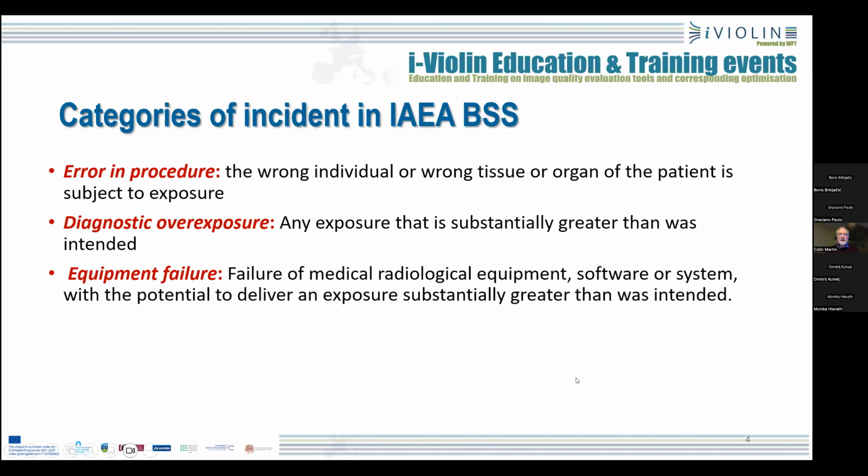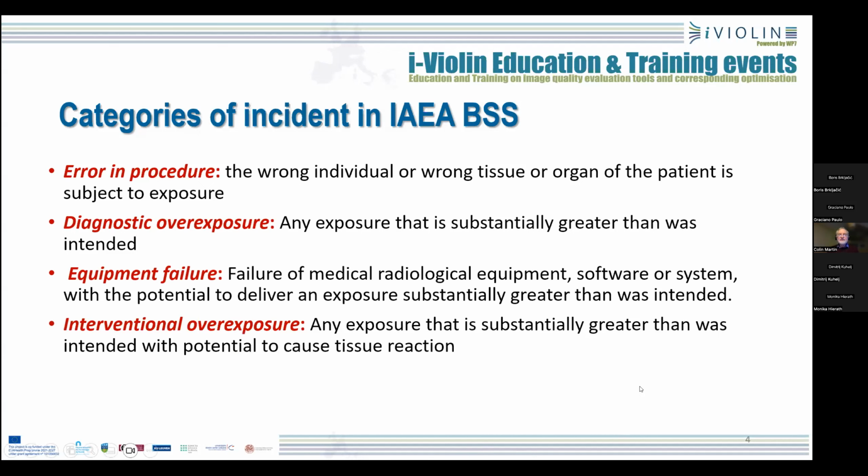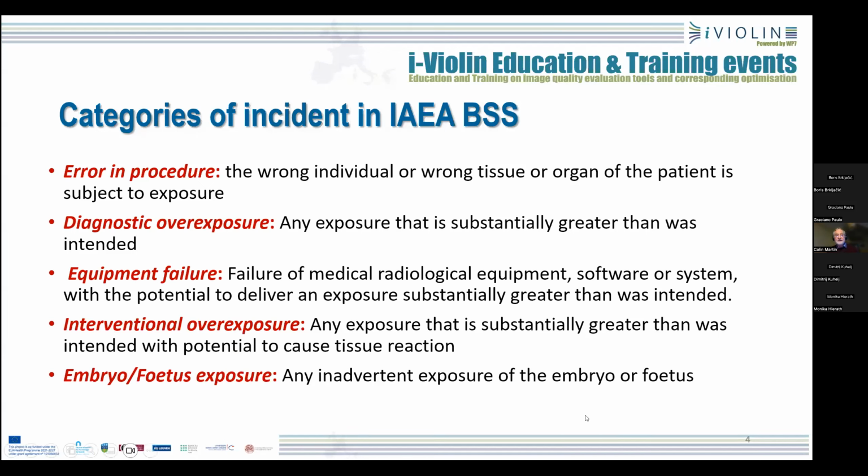An equipment failure, where there's failure of the medical equipment or the software or the system with the potential to deliver an exposure substantially greater than intended. An interventional overexposure, again, one which is substantially greater than was intended, but with the potential this time to cause tissue reaction. And also an inadvertent exposure of the embryo or fetus.